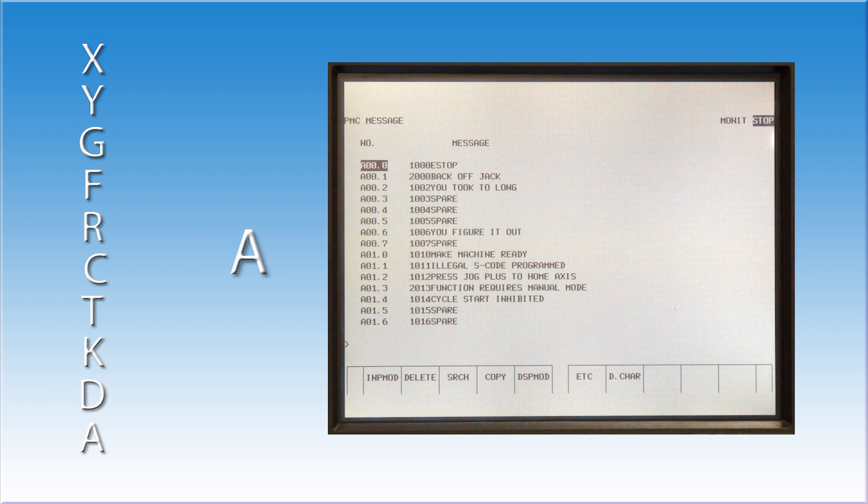The machine builder can assign a number to the alarm. Alarms in the 1000 range will stop the machine operation. Alarms in the 2000 range will allow the machine to continue running.